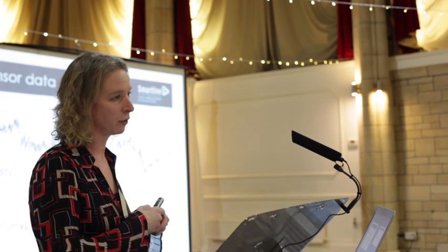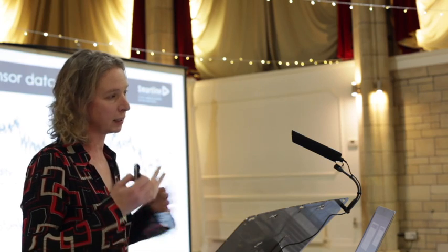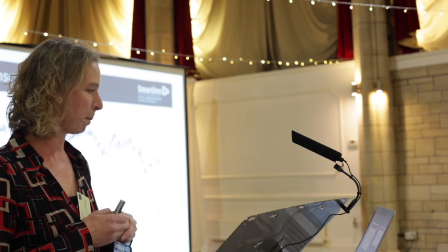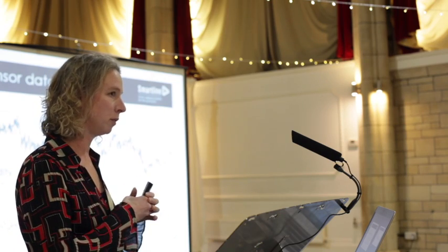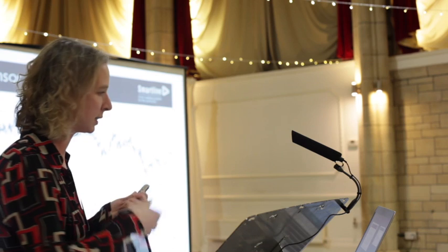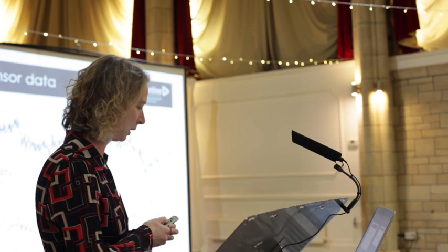And the humidity levels that are generally considered to impact on mould growth or on health are around 60 to 75% relative humidity. However, there's been a laboratory study that's shown if the relative humidity fluctuates a lot, so that you've got short, frequent bursts of high humidity, then there's less mould growth than if you've got longer cycles and longer drawn-out periods of high humidity.